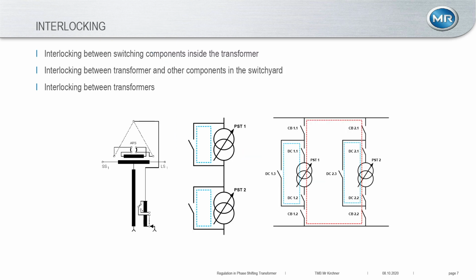And if we talk about interlocking, there are three different scenarios. The first scenario would be interlocking between switching components inside the transformer. If you have, as we see on the left-hand side, a two-core design with a booster application, you see that at the booster we have an advance-retard switch, and in the exciter unit we have a coarse-fine winding arrangement. Then you can only operate the advance-retard switch if you put the terminals of the booster to the ground connection with the on-load tap changer in the exciter unit.